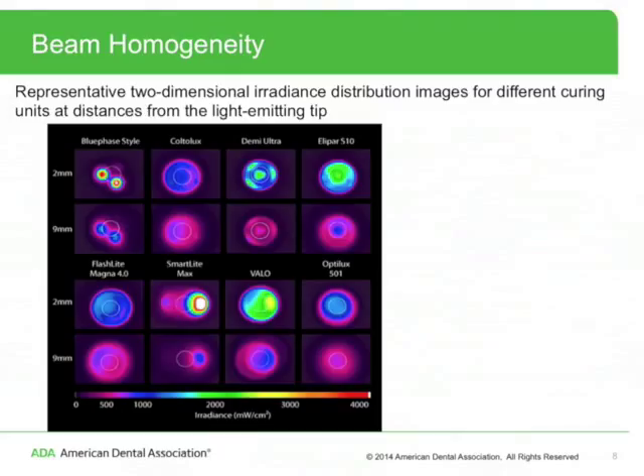Representative two-dimensional irradiance distribution images from different curing units at distances from the light emitting tip show that irradiance is not homogeneous across the light beams of the different LED curing units. The most homogeneous beam comes from the Optilux 501, which is a tungsten halogen curing unit. Single irradiance values reported in product literature for LED curing units can make it seem like the irradiance power emitted from a curing unit is uniformly distributed across its light beam; however, these images show that that is clearly not the case.